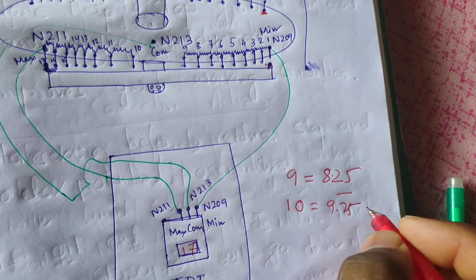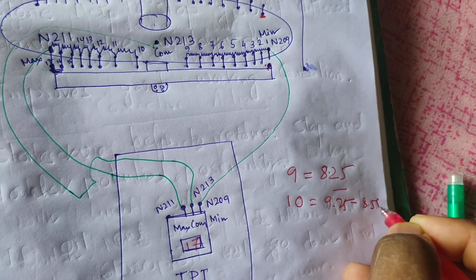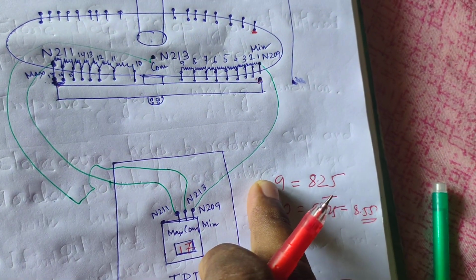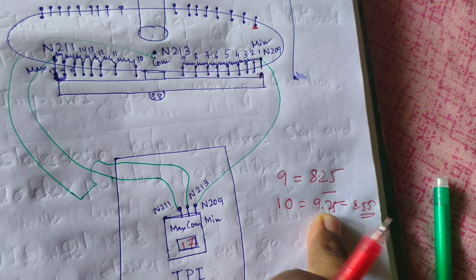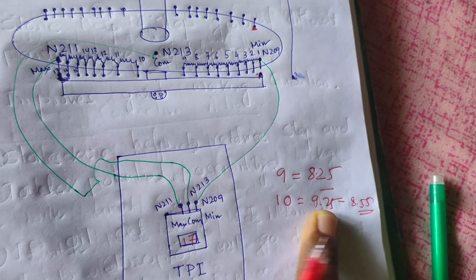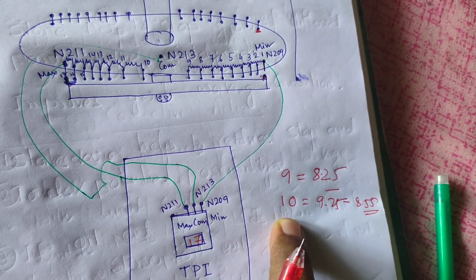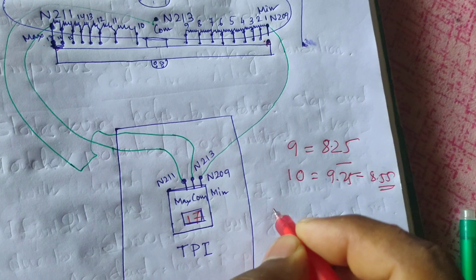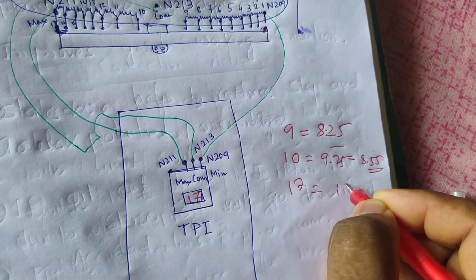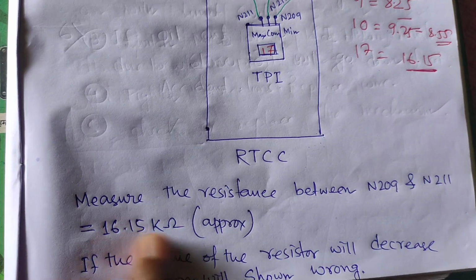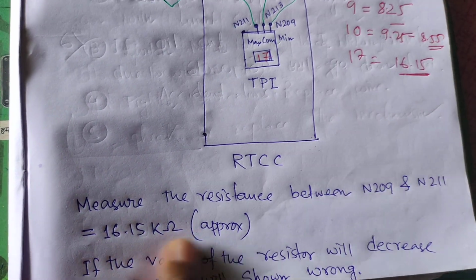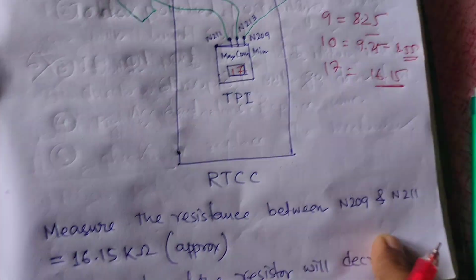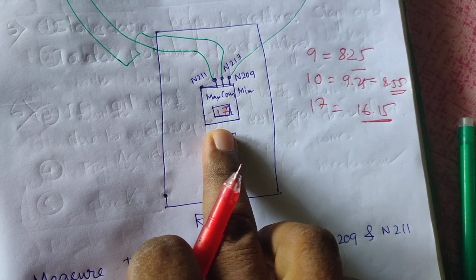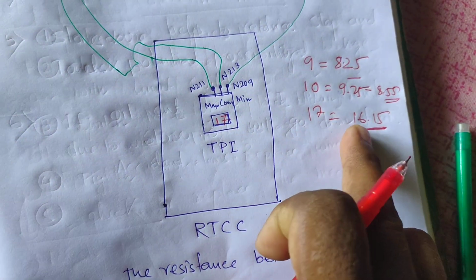Suppose the value decreases to 8.55, it will show 9. When it's near 9.25, it will show 10. For the 17 number tab, it should show 16.15 kilo ohms. If 16.15 kilo ohms is calculated, then tab position 17 will be shown on the RTCC. So it is a predefined value.